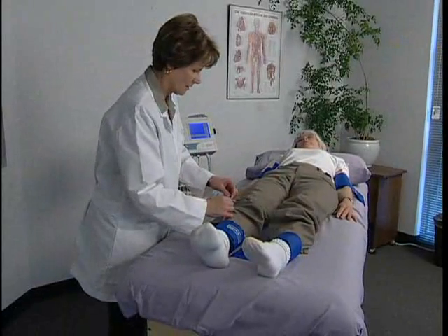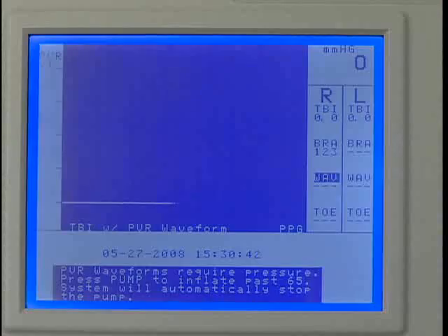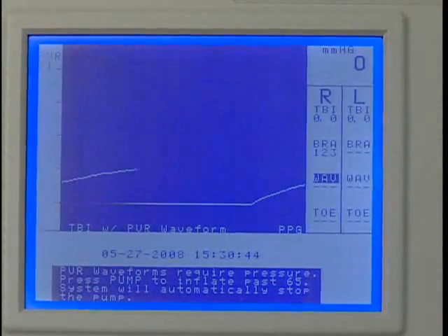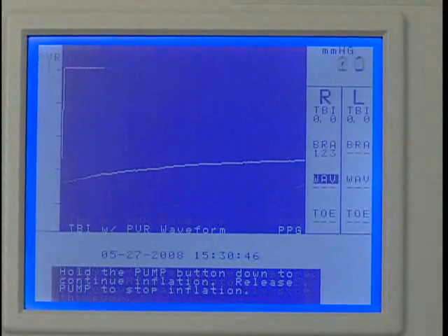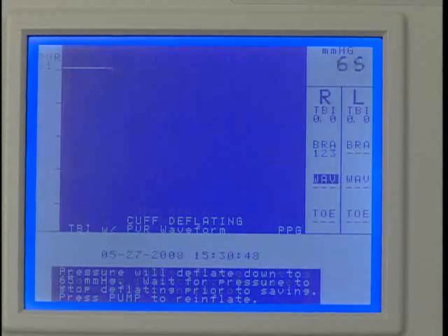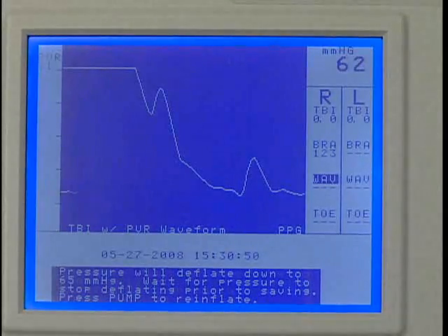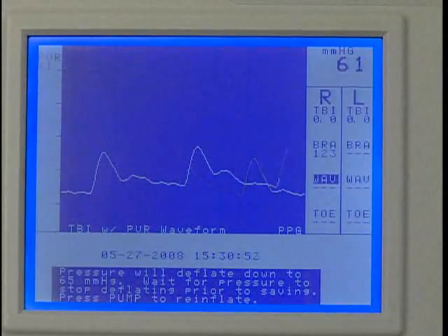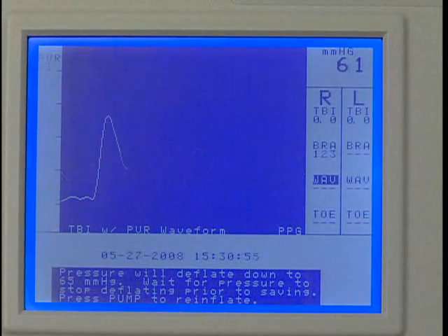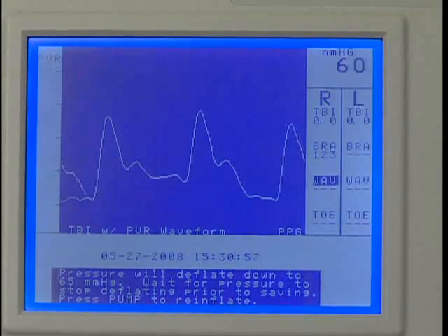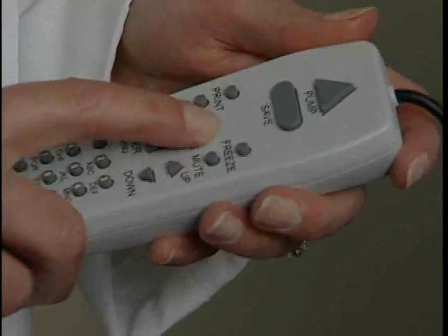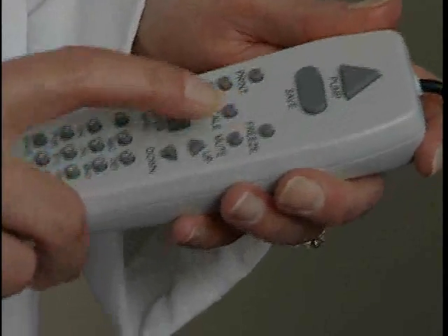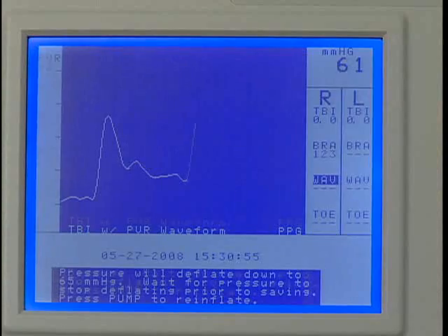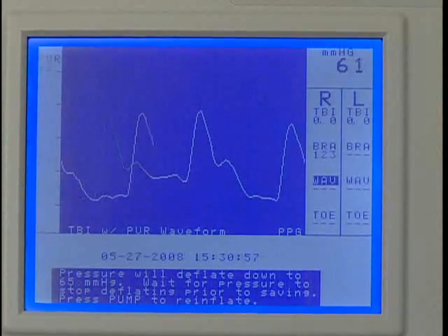Move the hose to the right ankle and connect it to the cuff. Press and hold Pump to inflate the cuff to 75 millimeters of mercury. Release when the inflation automatically stops. Pressure will deflate to 65 millimeters of mercury for optimum PVR. Wait for the cuff deflating message on the display to disappear. If needed, use the scale key to optimize the waveform. After the waveform stabilizes, press Freeze.